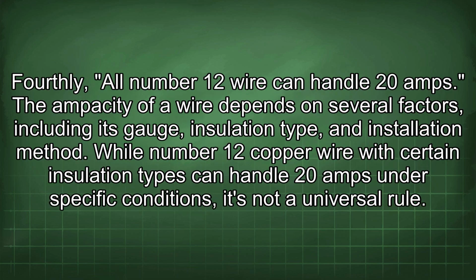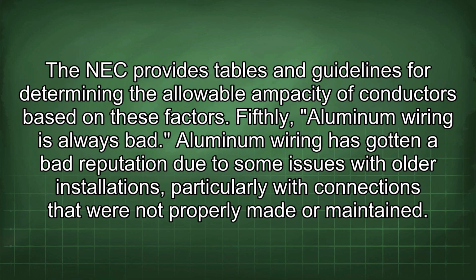Fourthly, all number 12 wire can handle 20 amps. The ampacity of a wire depends on several factors, including its gauge, insulation type, and installation method. While number 12 copper wire with certain insulation types can handle 20 amps under specific conditions, it's not a universal rule. The NEC provides tables and guidelines for determining the allowable ampacity of conductors based on these factors.